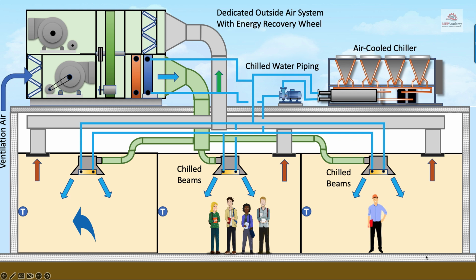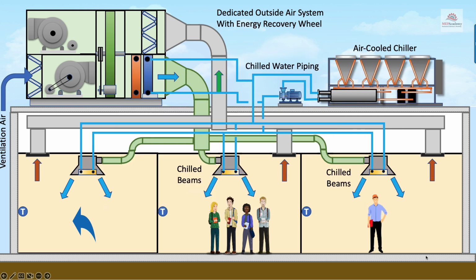Typically, the greatest dehumidification loads are from ventilation air, as removing the moisture out of the outdoor air for ventilation requires latent heat. See our video on humidification for additional explanations of humidity. The DOAS unit can provide heating, cooling, humidifying, and dehumidifying. The main purpose of a DOAS is to provide ventilation air for acceptable indoor air quality and to offset exhaust air used for bathrooms or other purposes.